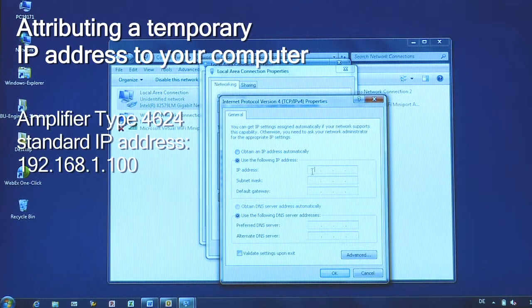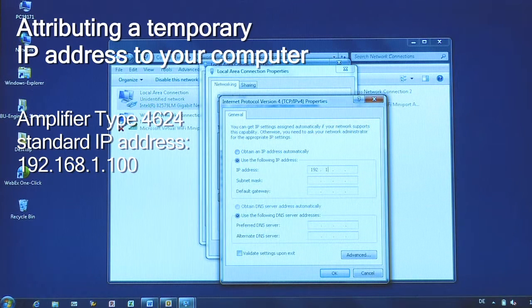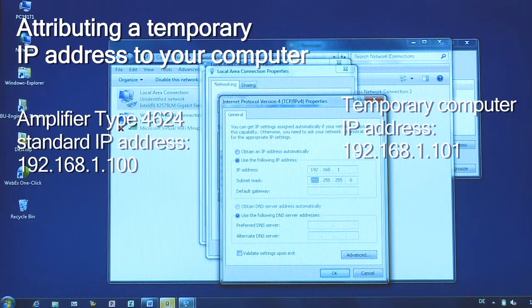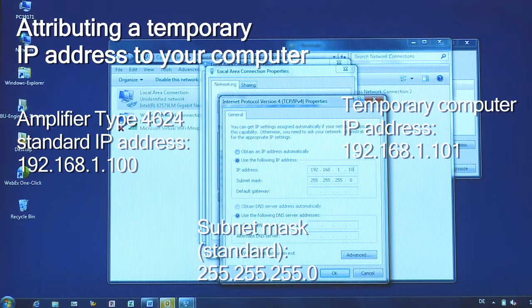Our amplifiers have a standard IP address: 192.168.1.100. For your computer, preferably choose almost the same address but change the last three digits — instead of 100, put 101. There is also a standard subnet mask. If it's not automatically set up, enter the address manually.